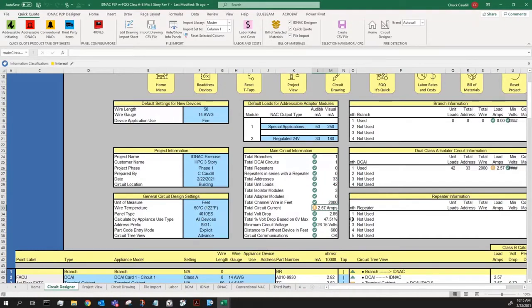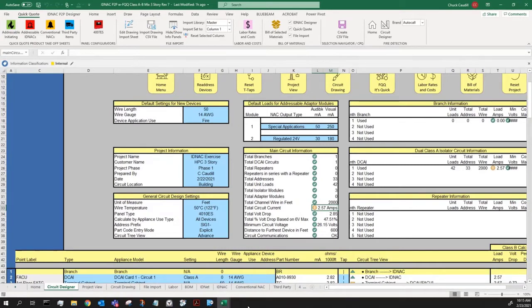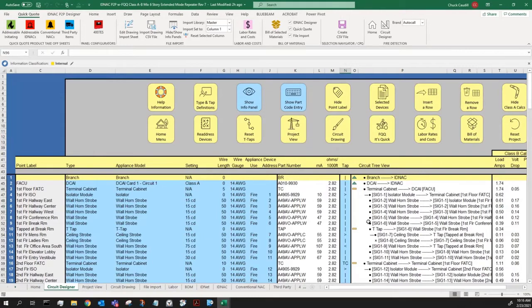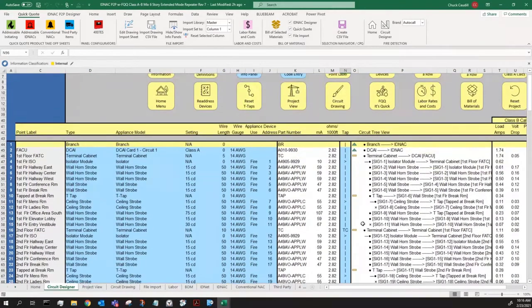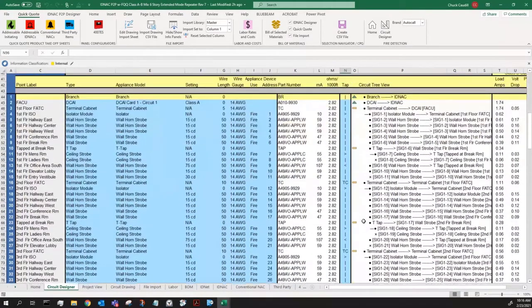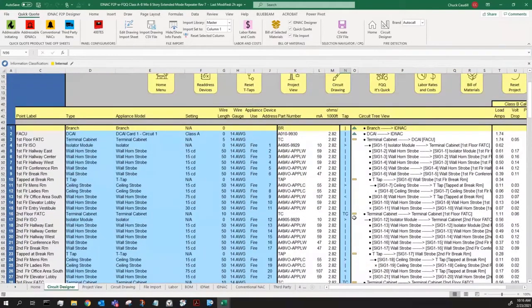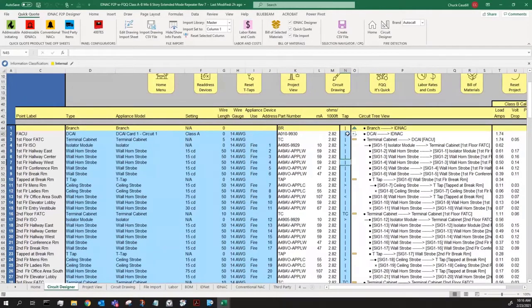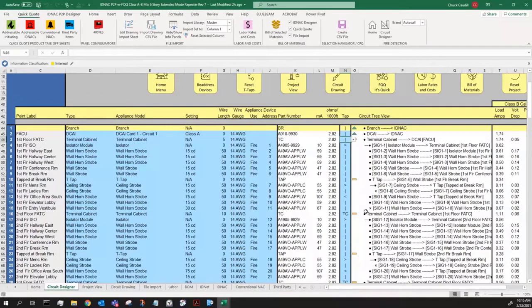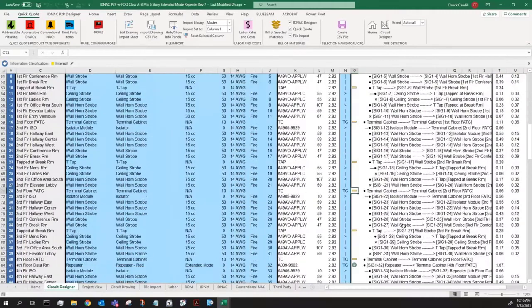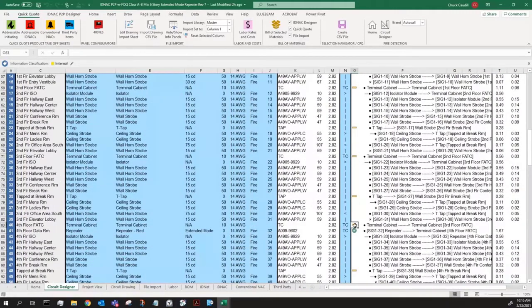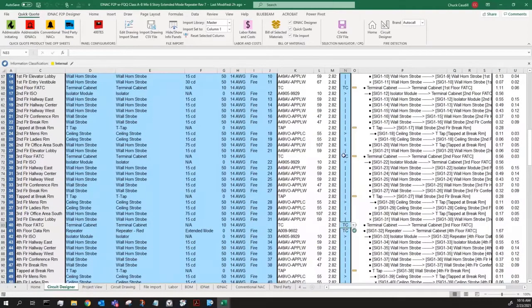Can I throw a repeater in here? You can, if you do it in the proper method. So I've got another exercise here. We're going to throw three more floors onto this. It's just like the one we just looked at. Instead of being a three-story, it's a six-story. Well, where's my power for the fourth, fifth, and sixth floor going to come from? We're going to throw a repeater in. First three floors are just as we did previously. DCAI with the terminal cabinet on the first, on the second, and on the third floor. When I get up to the fourth floor, I'm going to throw another terminal cabinet. And again, it's tied to the TC down the floor below.